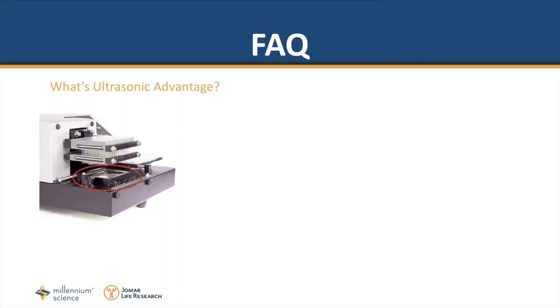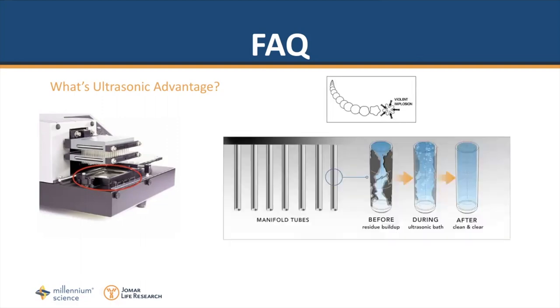Now some frequently asked questions. What is ultrasonic advantage? The ultrasonic advantage is the in-built cleaning system in the biotech plate washers. When the manifold tubes are in the metal reservoir, ultrasonic energy creates the repeated and violent implosion of bubbles within the cleaning liquid and this in turn removes any stubborn buildup of salts and protein.